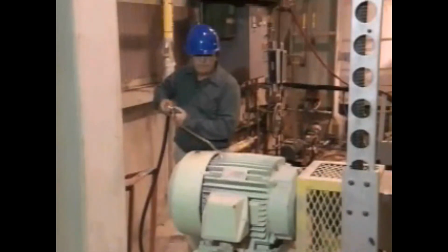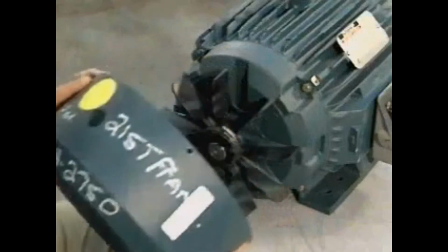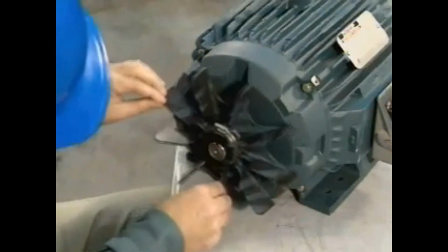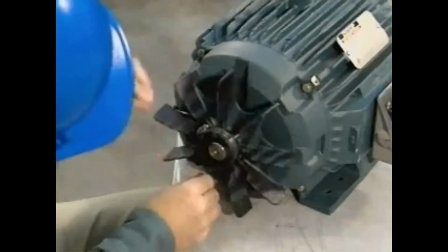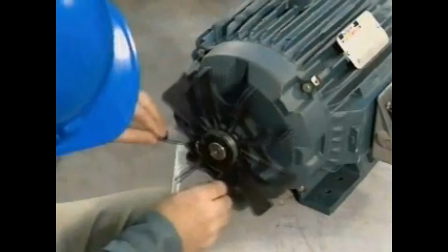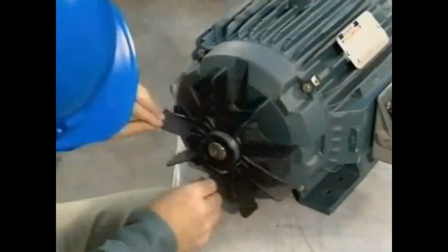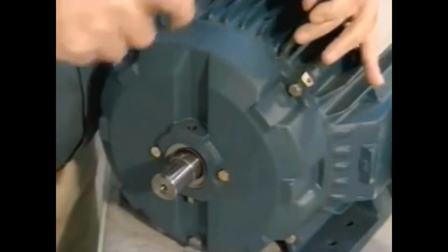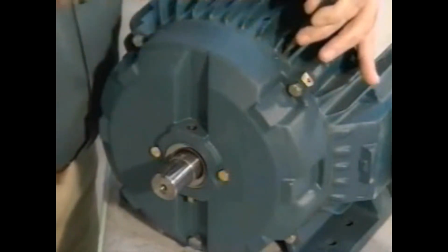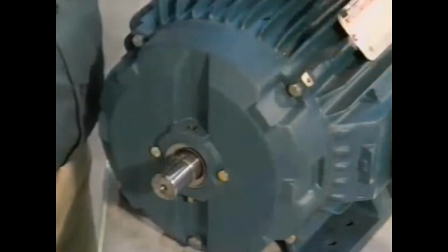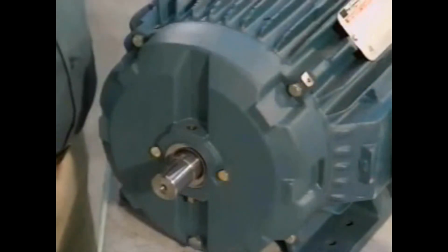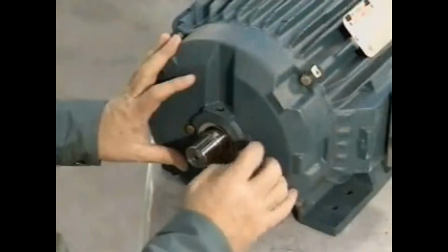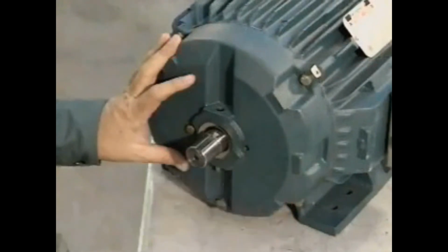Select Next to continue. Motors are disassembled by starting from the ends and working toward the center. When disassembling a motor, use techniques that will protect both the motor and yourself, and that will make the reassembly job easier. Begin disassembly of the motor by match-marking the end bells and stator housing to provide reference marks for proper end bell replacement later. Remove, bag, label, and store the bolts.